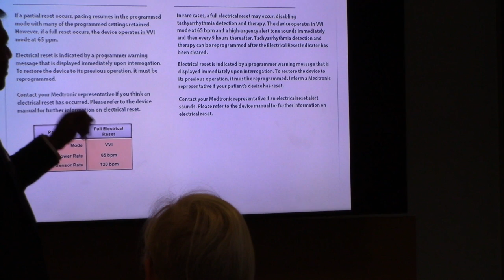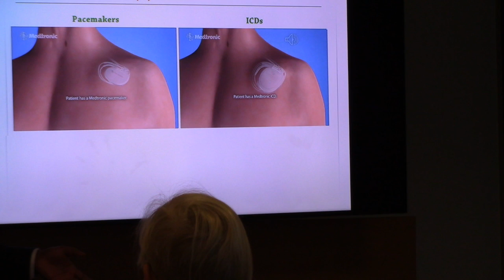So it actually makes a noise, the pacemaker? The ICDs. The pacemakers will not make that noise. It will just operate in VVI 65. So just like, as if a magnet was put in and it's at end of life or something. But it's not going to.